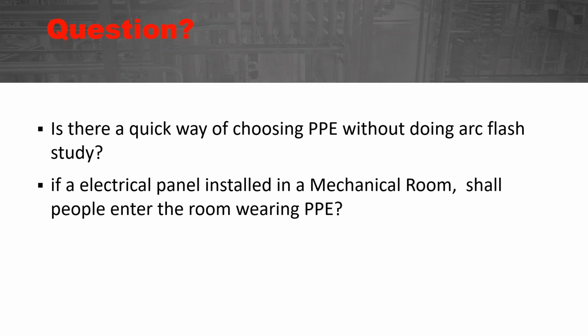So the answer to the first question: NFPA 70E provides a secondary method to determine arc flash PPE if certain conditions apply. This is called the PPE category method, and it's in accordance with Article 130.7 C15. Basically it says if you have this voltage, this current, and this protective device operating time, this would be your PPE rating. So that can be used as a method to choose PPE. That is typically considered a more conservative method than the actual incident energy analysis, because the analysis is a little more targeted and calculated. But that is one method to determine PPE besides a full-on incident energy arc flash study.